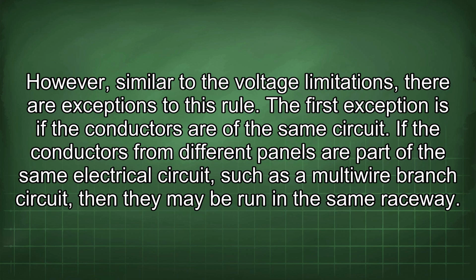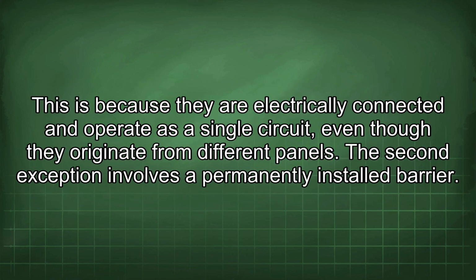The first exception is if the conductors are of the same circuit. If the conductors from different panels are part of the same electrical circuit, such as a multi-wire branch circuit, then they may be run in the same raceway. This is because they are electrically connected and operate as a single circuit, even though they originate from different panels.